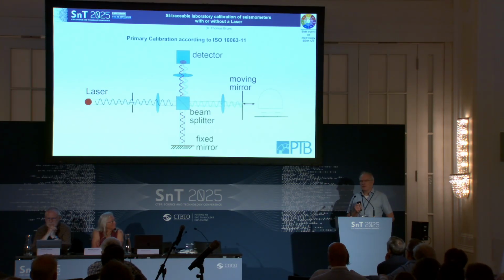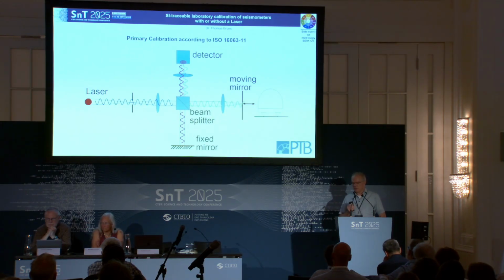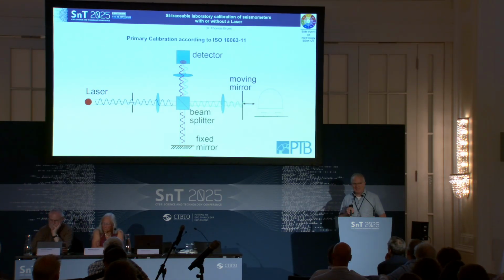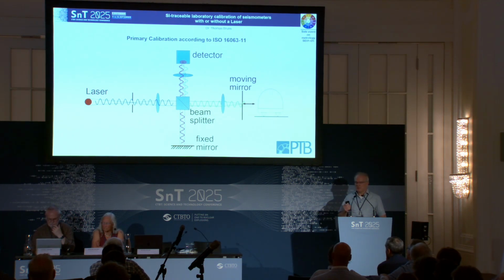For the laser interferometric primary calibration, there's a long-standing standard, ISO 16063-11, calibration by laser interferometry, and this is just a sketch of the principle using a Michelson interferometer as a demonstration. They are not used often nowadays, but nevertheless, they are good to introduce the topic. You have the seismometer connected on a precision shaker table, as Horst named it, with a moving mirror attached to the table. And you have a laser interferometer: a laser source that gives you the beam that is divided into a reference beam that is reflected by a fixed mirror, and the measurement beam that is reflected by the moving mirror on the shake table. They are superposed on the detector, and there you have an interference pattern, so you have a light-dark change on the photodetector when the moving mirror moves.